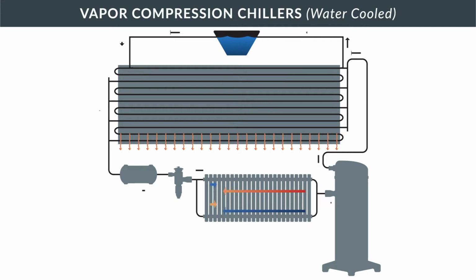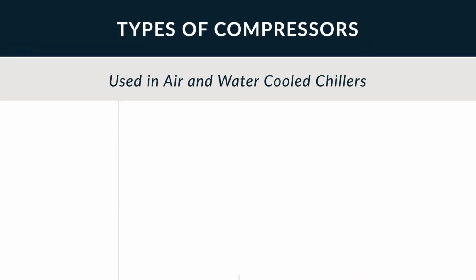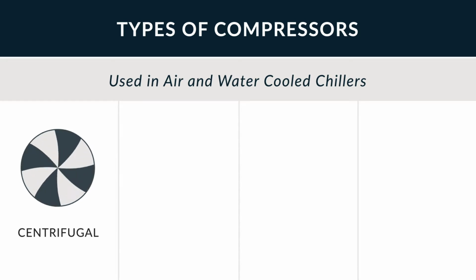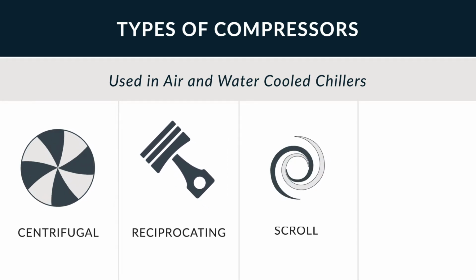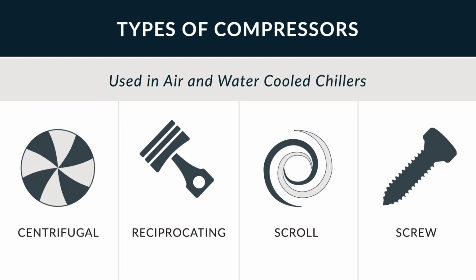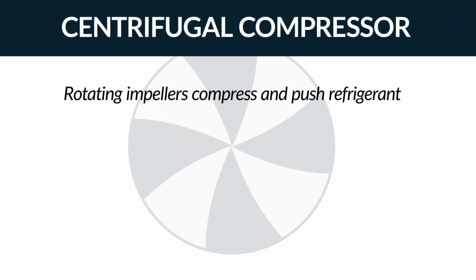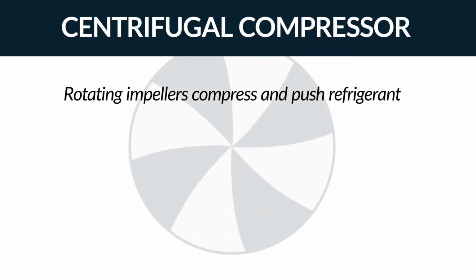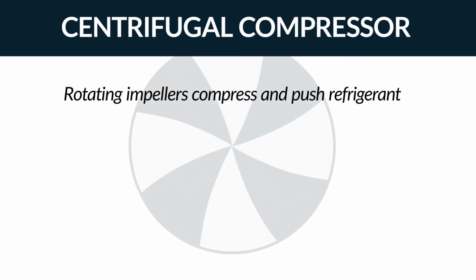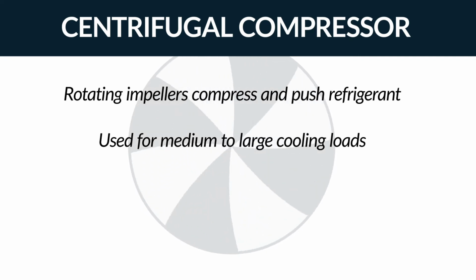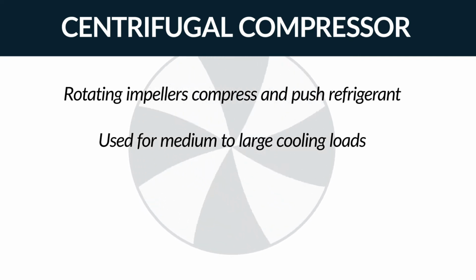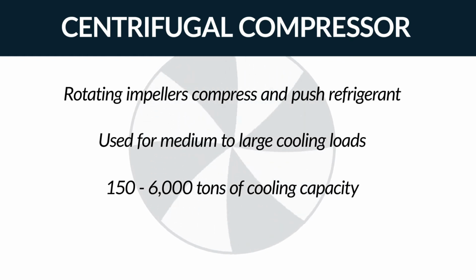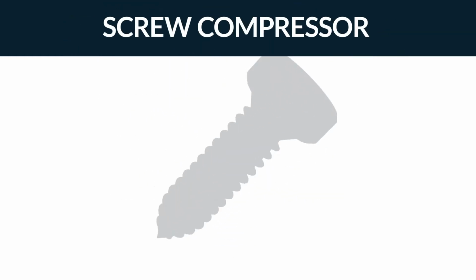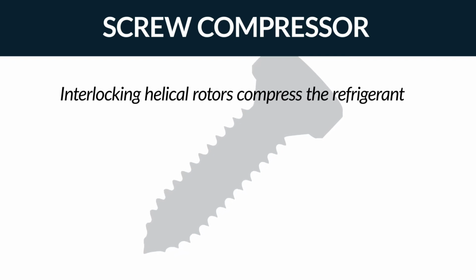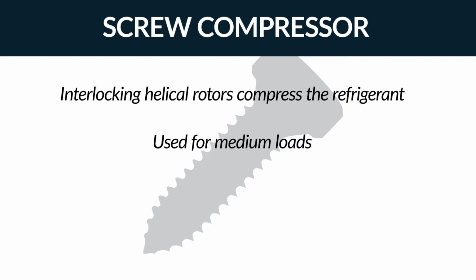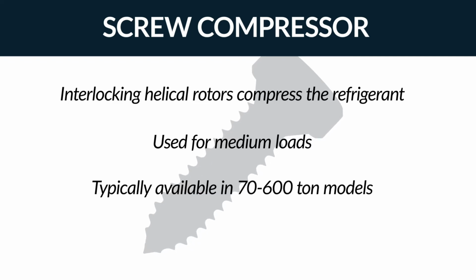Air and water-cooled chillers are further categorized by the type of compressor technology used: centrifugal compressors, reciprocating compressors, scroll compressors, and screw compressors. Centrifugal chillers use rotating impellers to compress the refrigerant and force it around the refrigeration circuit. Centrifugal chillers are often used for medium to large cooling loads and are available from 150 to 6,000 tons of refrigeration. Screw compressors use 2 interlocking rotating helical rotors to compress the refrigerant. These chillers come in 70 to 600 ton models.